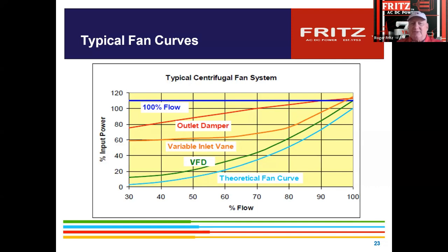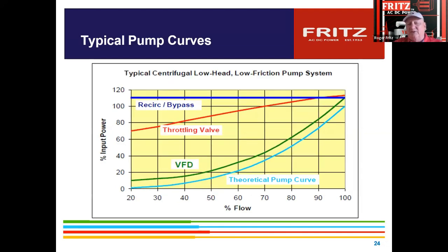has a pump curve. And so there's a sweet spot on a pump where it was originally designed to run in a certain range and actually be at its optimal efficiency, up around 65-70% efficiency of the pump. If you go too far below or too far above, the curve goes off and sometimes it'll drop down to 30%. And so you forfeit some of your savings. So it's definitely important to do an analysis well before we start, on where we're at on the pump curves, and also on the vanes and those kinds of things. It slows your ability to save.